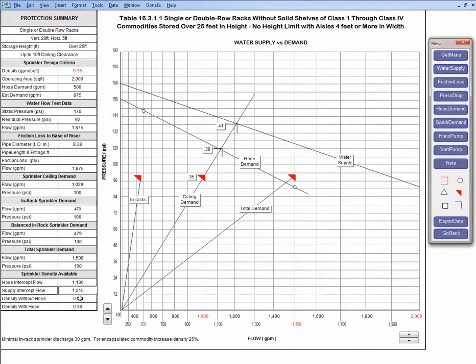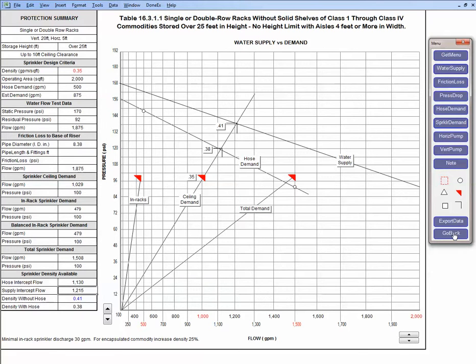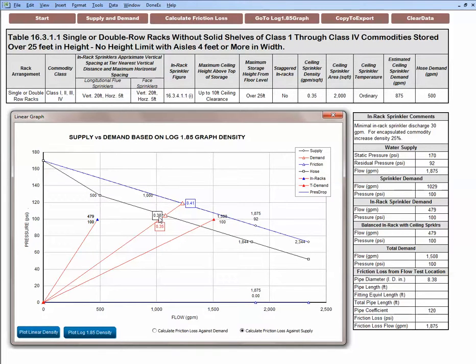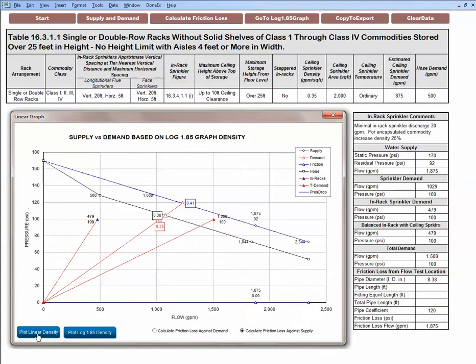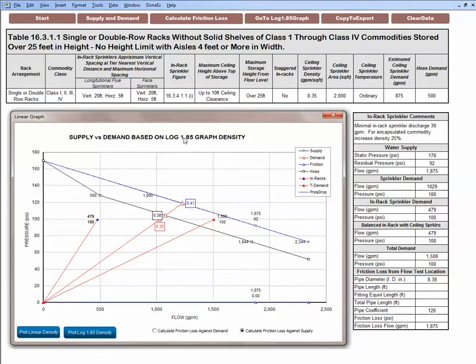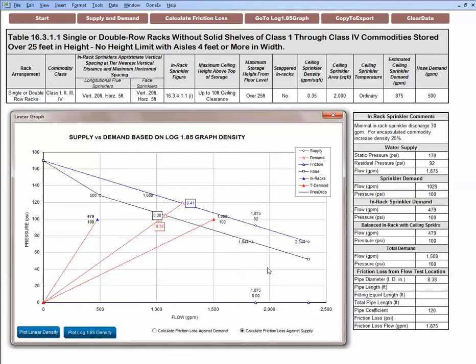I could go back and I want to click this blue button plot log 1.85 density. I click it and it changes slightly to 0.38 with hose and 0.41 without hose. The linear one is less conservative and it shows 0.37 and 0.42. So when I click the plot log 1.85 density, even the title changes. I have linear graph density when I plot log 1.85, it shows that I selected and pulled the density for log 1.85 and put them on the linear graph. Now the linear graph is as accurate as a log 1.85 graph. Now I could export the data to a loss prevention report.